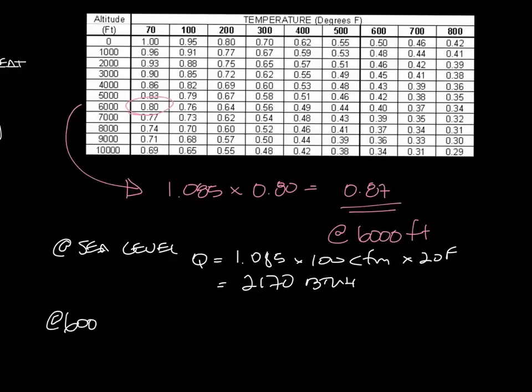Now at 6,000 feet, our equation becomes Q equals 0.87 times that 100 CFM times 20 degrees. And that equals 1740 BTU.